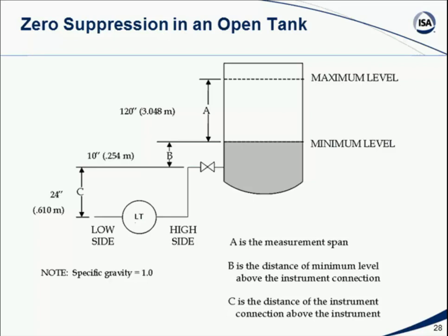But what is the pressure that's being felt on the high side of this pressure transmitter? Well, it's certainly going to be the amount of fluid on this diagram called B. So we've got our tap-off point, and the fluid is B inches above that tap-off point. So we've got certainly B inches of fluid. But that's not really what we have, because this transmitter device is not only located away from the tank, but it's also C inches, or 24 inches, down below the level of the tap-off. So the point in fact is the liquid column that's attached to the high side here is a column of fluid that's B plus C, in other words, the fluid in this impulse line, of elevation. So actually my starting point for measurement here is not 0, but C. So even if the tank were all the way down to where the fluid just dropped right down to where my tap-off point is, I still have 24 inches, or this C value, of fluid in this impulse line that's pressing against the pressure transmitter.